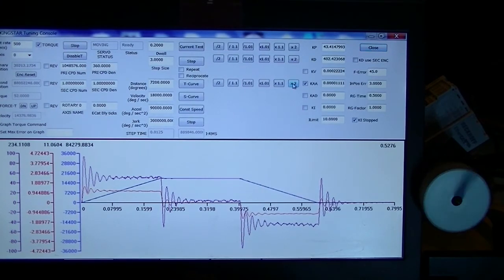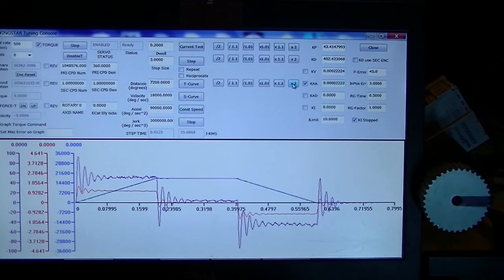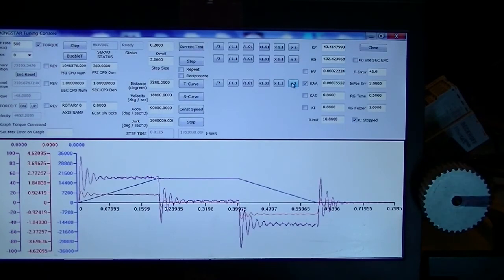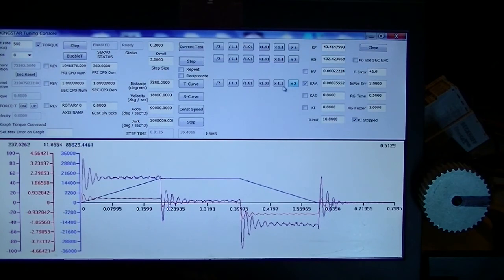And we're going to double it and double it until it starts to do something. I could calculate this, but it's just as easy to continue to double it. It's already moving. I'll do one more doubling. I'll now switch to 10% moves, and I can do a series of these. I can just click it a few more times, and then slowly, I might have gone too far on that one, so I'll back off by 1, and I'll go back by 1%, and I think that's as good as we're going to get.